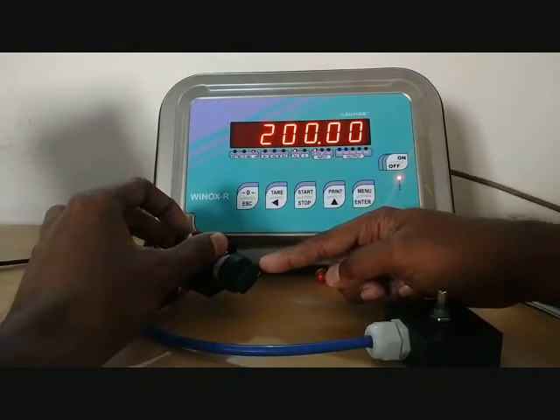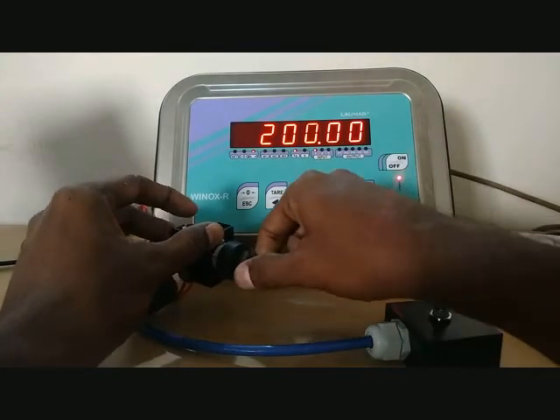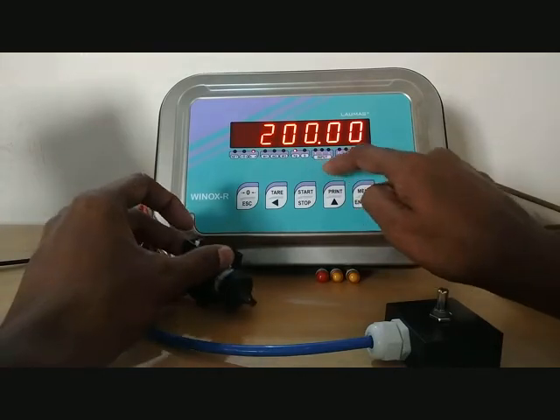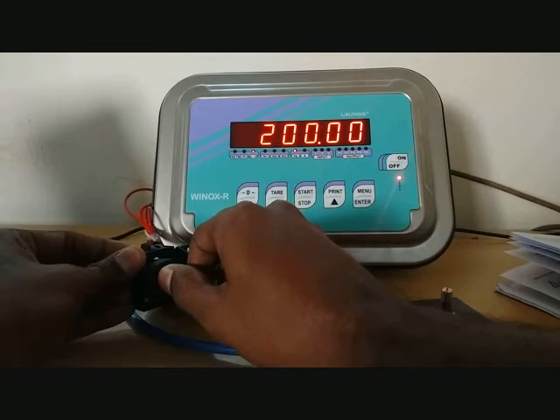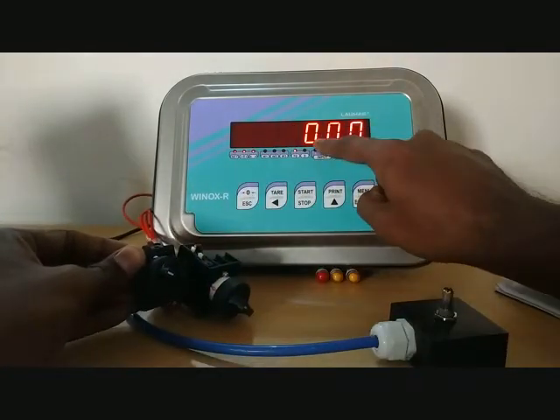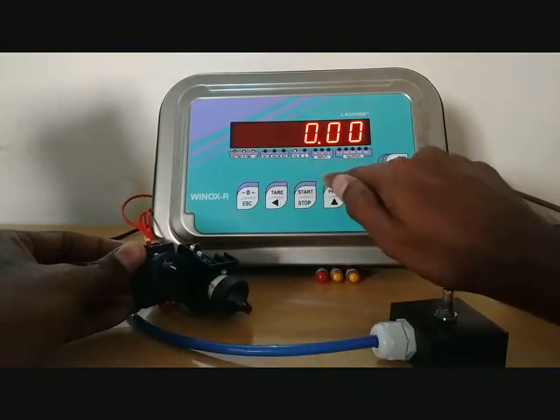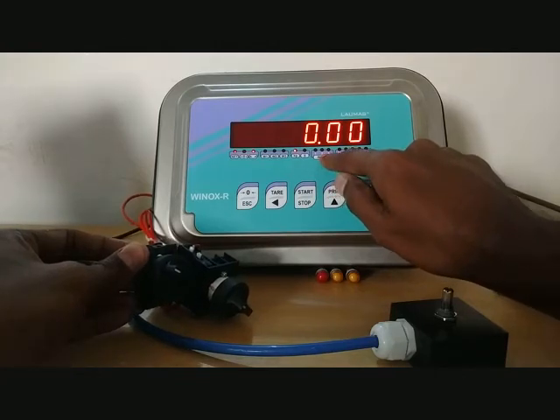If digital input 1 is enabled you will get digital input 1 is high. If it is disabled you get digital input is off. Now I am enabling digital input 2 — that is for taring. So now the value is tared and the display goes to net mode. The input is off. We have given a momentary input for taring.